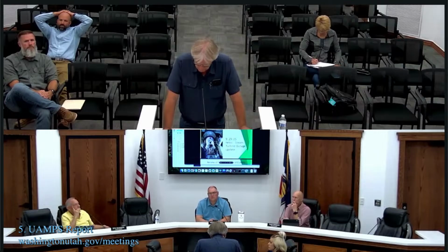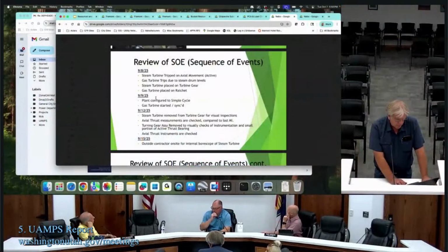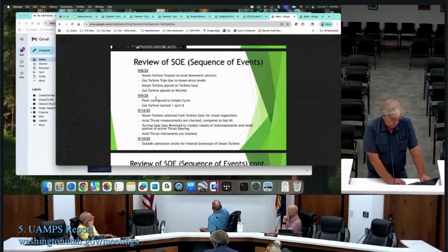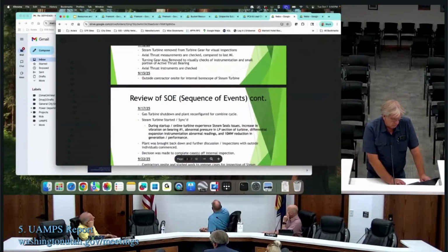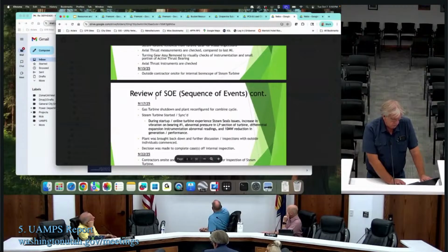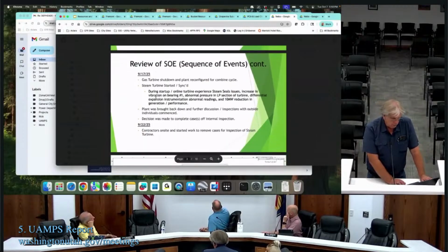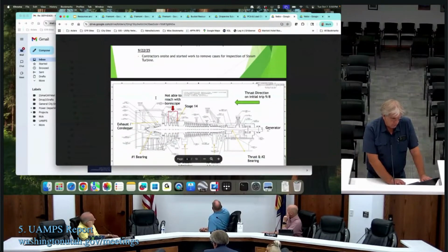Probably the biggest thing on the UAMPS side was the NEBO project. In mid-September, around September 8th, they had the steam turbine trip. They took it offline for a period, did some bore scope inspections, couldn't see anything with what they could see, tried starting it again, and couldn't get it up to capacity, so they shut it off and had to do a much deeper dive into the unit.